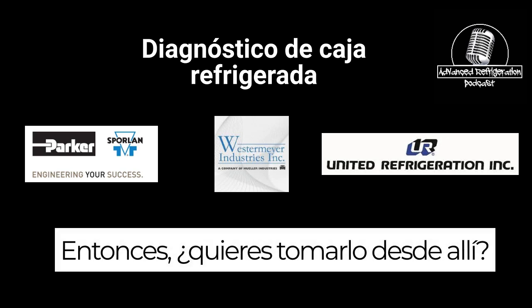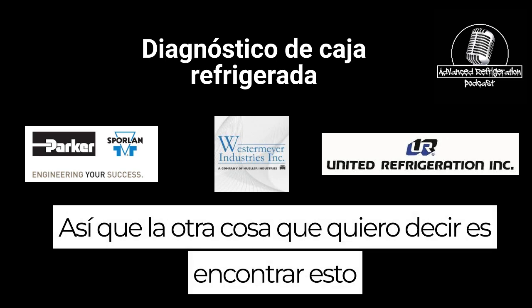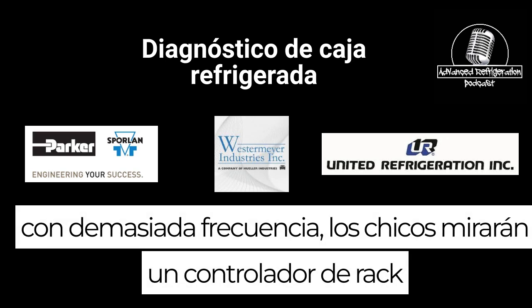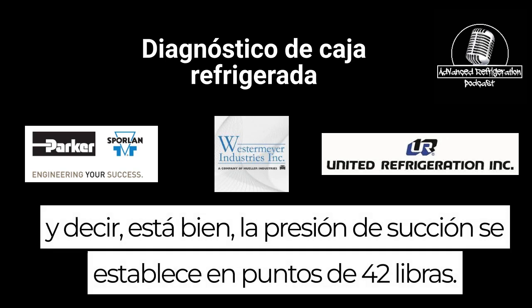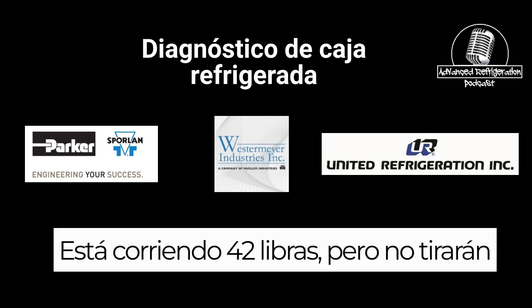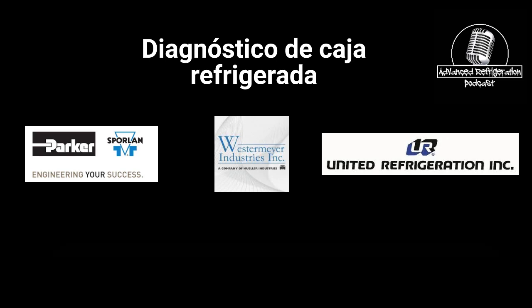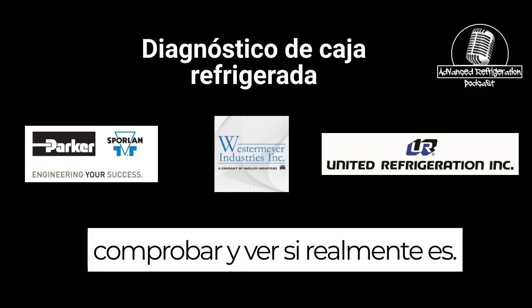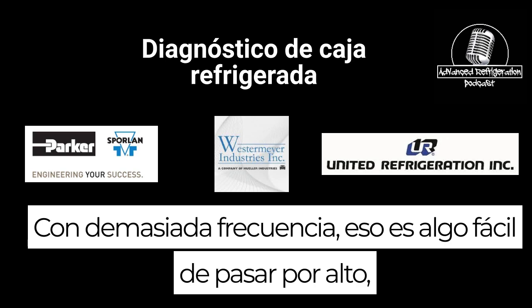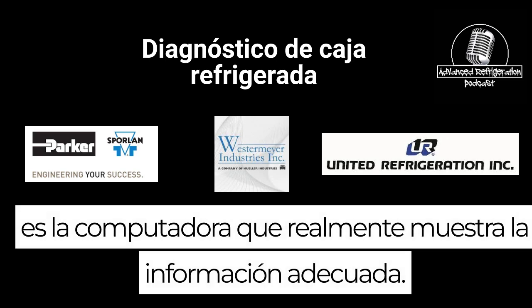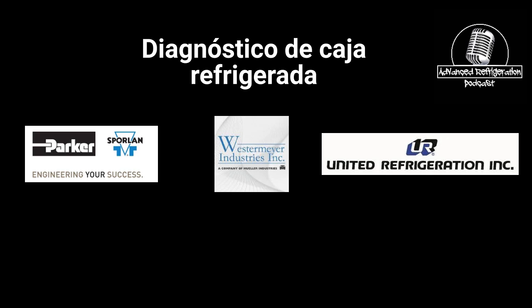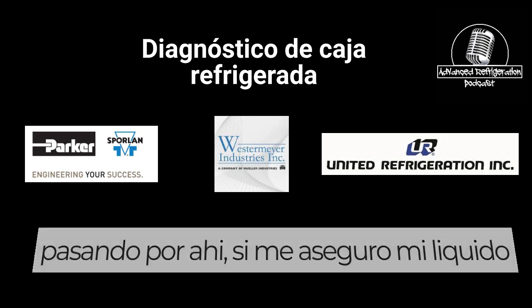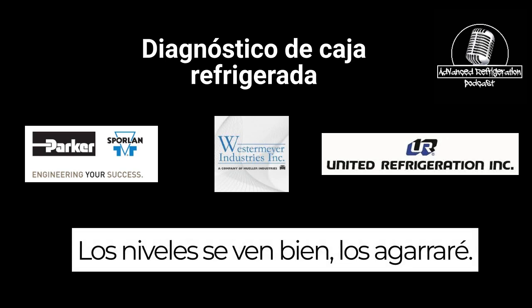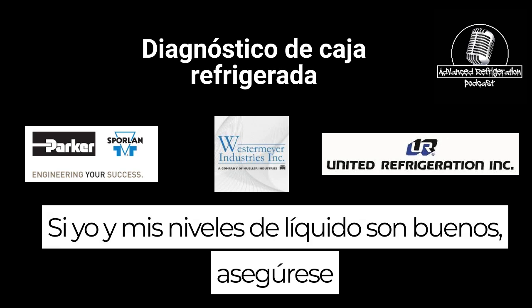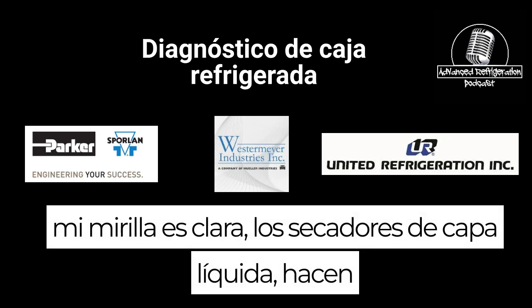So you want to take it from there? Yeah. Go ahead. The other thing I want to say is I find this all too often: guys will look at a rack controller and say, okay, the suction pressure set point's 42 pounds, it's running 42 pounds, but they won't throw a gauge or a transducer on there to check and see if it actually is. That's a simple thing to overlook, is the computer actually displaying the proper information?